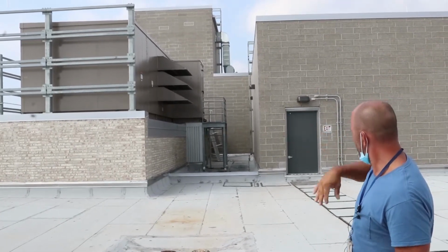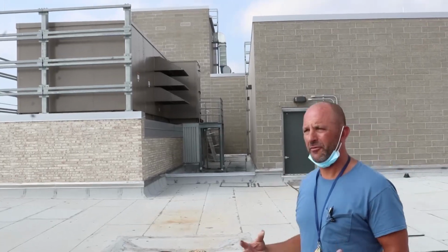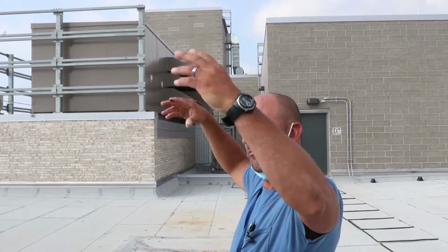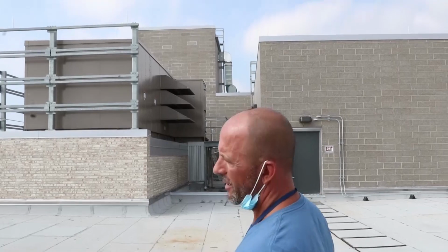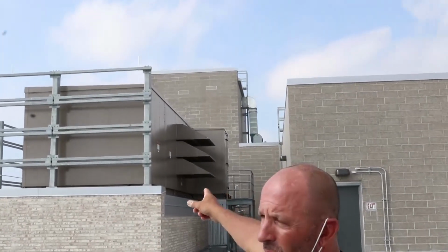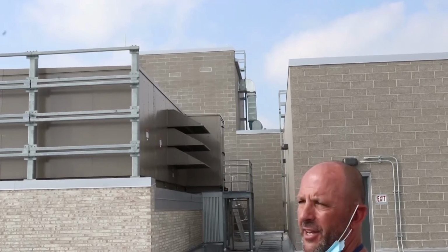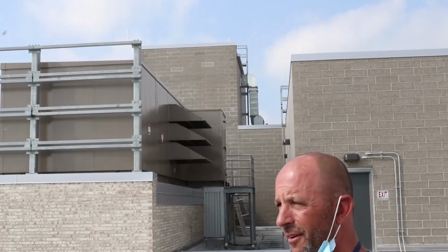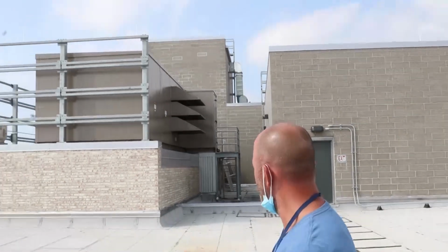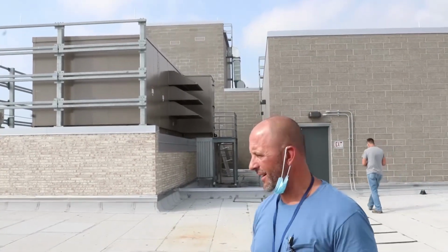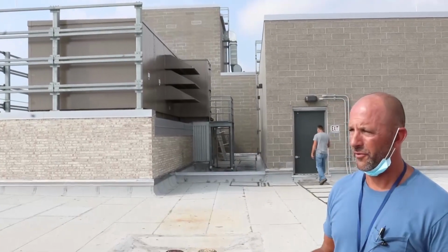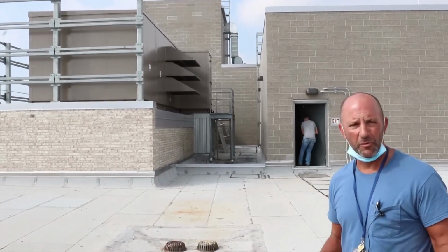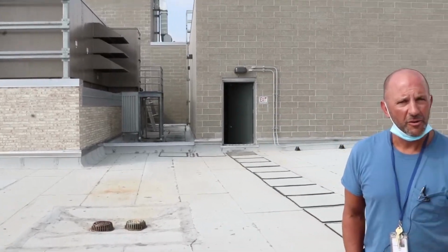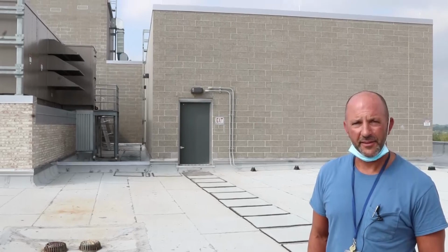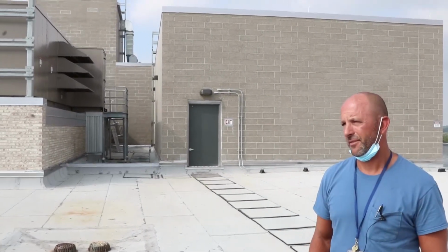When we go through this corridor and down, there's another, bigger fan that pressurizes the whole shaft from the 5th floor down to the lowest level. That one takes fresh air in and pressurizes the room itself, while the other one on the ground gets blown into the shaft to pressurize it. In case of fire, it keeps the smoke out of the elevator. Those are set by the balance of the speed. I'm not sure if that's automatic or if the fireman keys it, I guess it's automatic. That would be more of a fire alarm question, but I'm assuming in a fire those things just go on and pressurize the shaft.